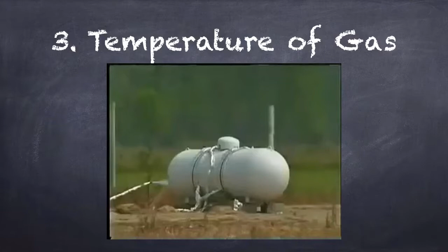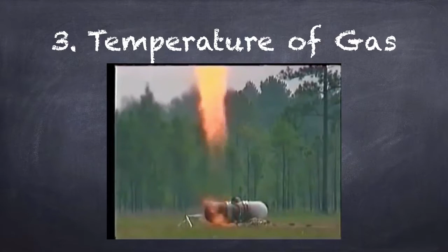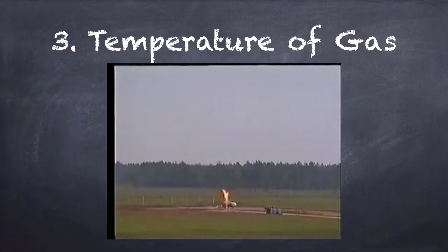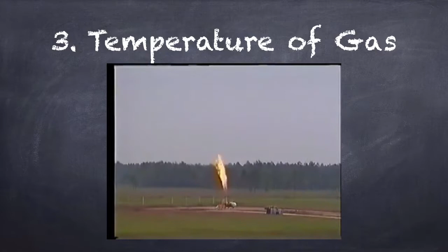When a tank is exposed to sustained heat, such as from a fire, the liquid within the tank is forced to boil or vaporize, resulting in increased pressure in the tank. To prevent overstressing the tank, the relief device activates, venting the excess pressure. As pressure decreases in the tank, the valve begins to close. With continued heating, pressure again builds, causing the relief valve to reopen. Where flames impinge on the tank below the liquid level, the liquid absorbs the heat, allowing the tank metal to remain at a safe temperature. With continued relief valve operation, the liquid level drops, exposing a greater area of the tank to the effects of heating.